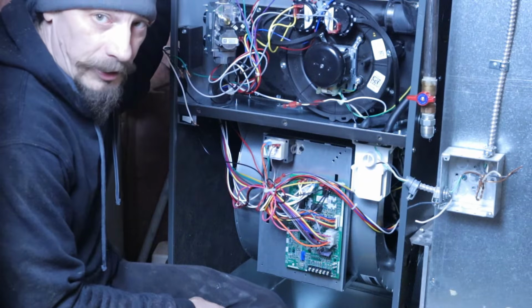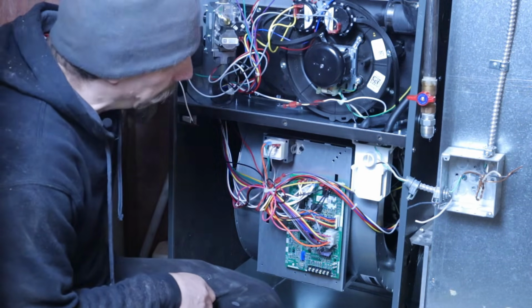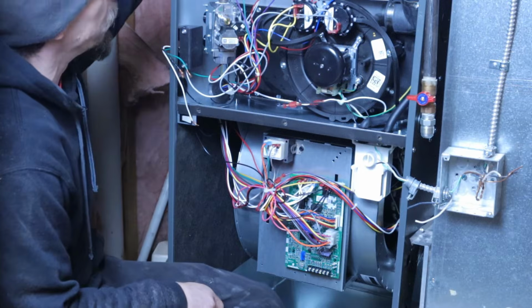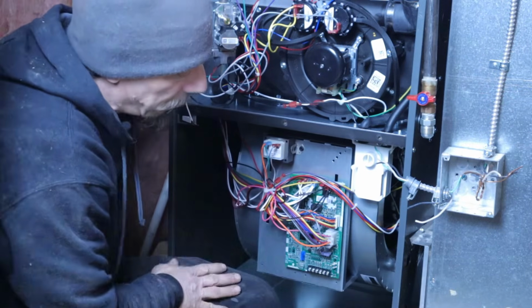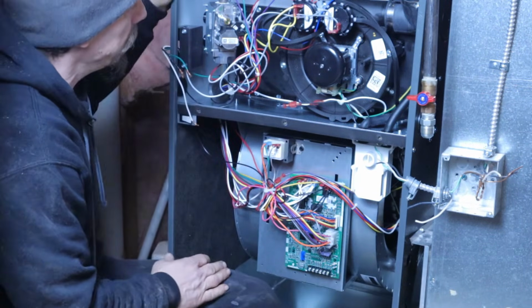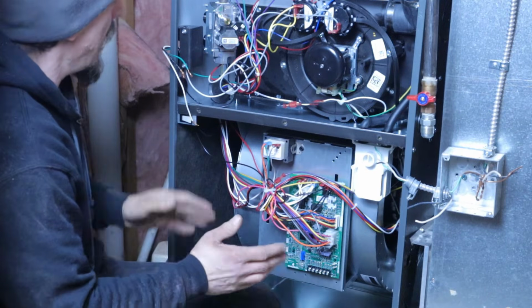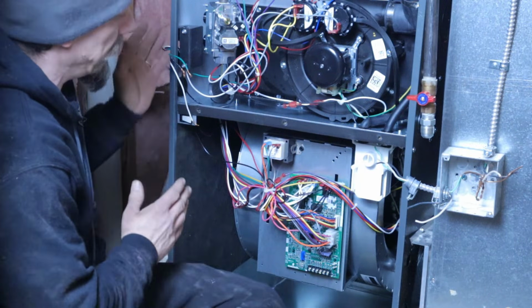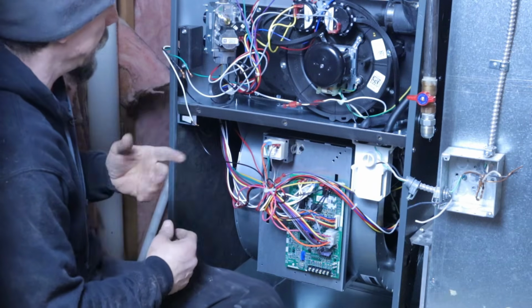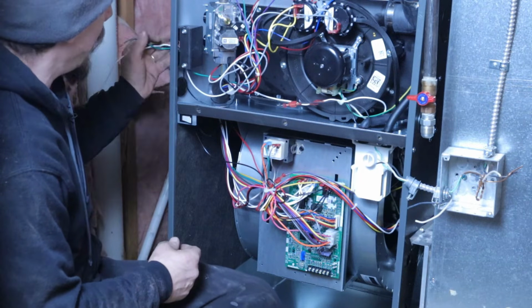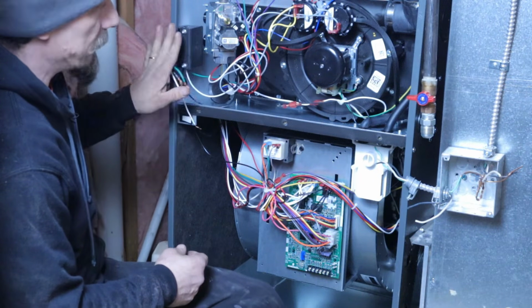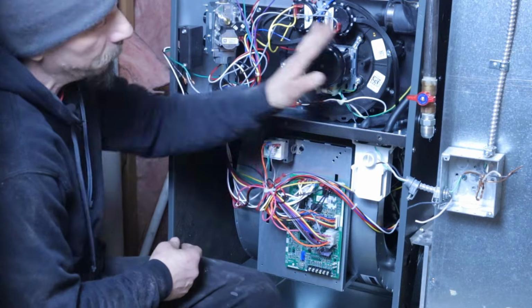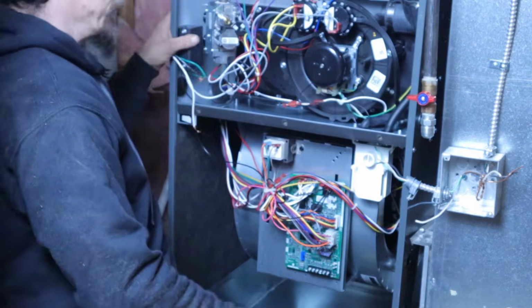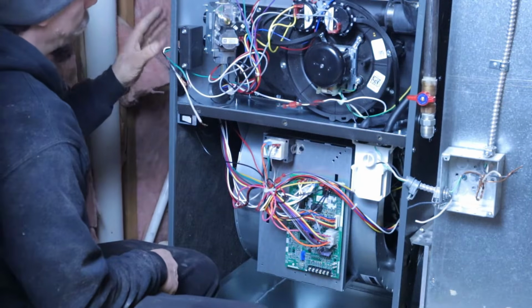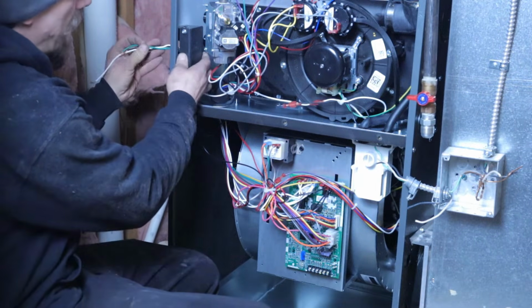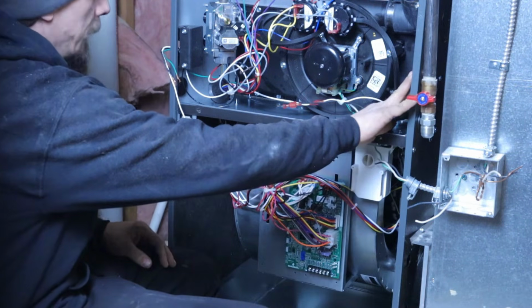All right, so we got our unit in place. We got it up on the blocks. It's lined up with the coil. Our return lines up. We're just going to screw that back in. And basically what I'm looking at now is where the gas and the electric and all that stuff needs to be reconnected. So on this unit, we have the power connections on the left side here. I can move it over to the right. So what I'm going to do is we're going to move the power, we're going to move this box over to the other side here.